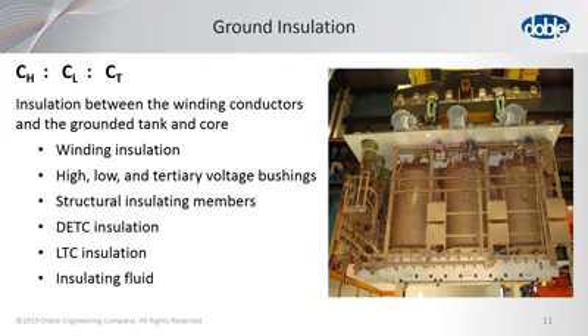Now this is a good picture, and it shows the de-energized tap changers right here. Now that's the DETC. As the name implies, the transformer must be de-energized to move this tap changer. And the overall test tests the insulation from these devices to ground, right?